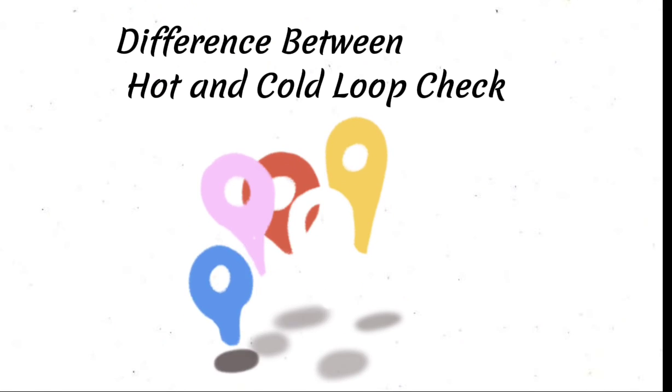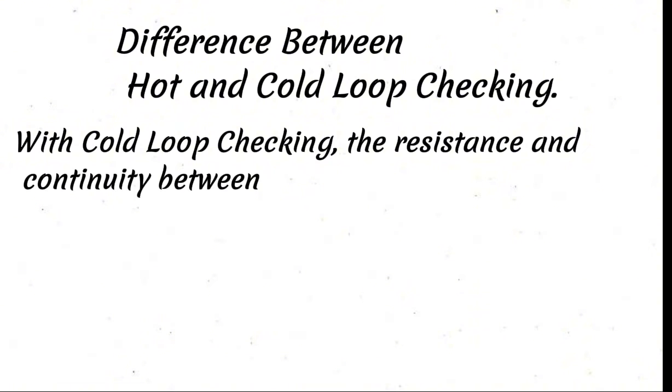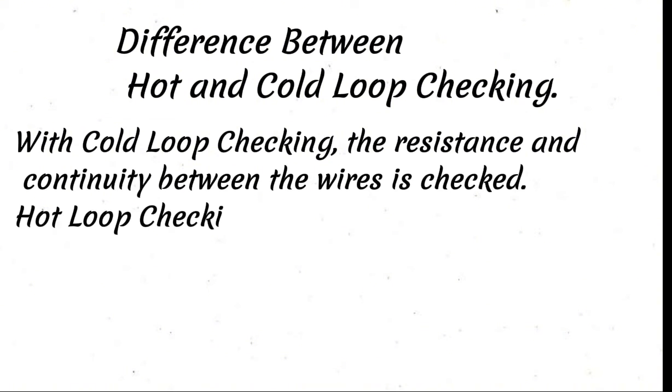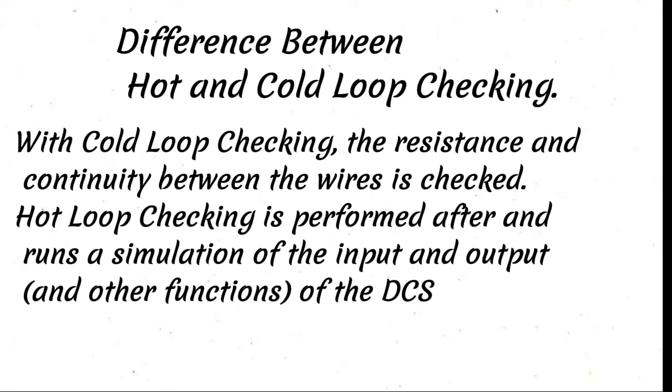Difference between hot and cold loop checking. With cold loop checking, the resistance and continuity between the wires is checked. Hot loop checking is performed after and runs a simulation of the input and output and other functions of the DCS or PLC controller.